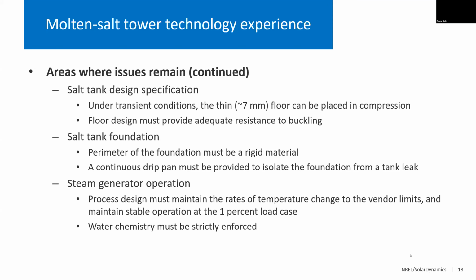The other thing is that the process design needs to be able to control thermal loads at the 1% range. It sounds like an odd requirement, but the heat exchanger sees this 1% load case every day. And it's important to make sure that the rates of temperature change and also the number of thermal cycles that occur at the 1% load case are under control. It's easy to have oscillations in temperature if your process control isn't tight. And these oscillations in temperature in combination with high rates of temperature change will definitely cause the heat exchangers to fail. We've seen that in more than one project.